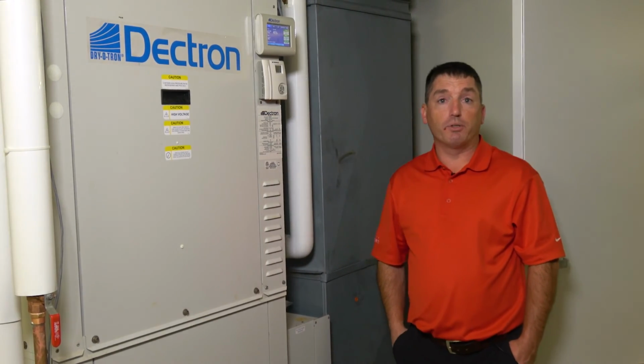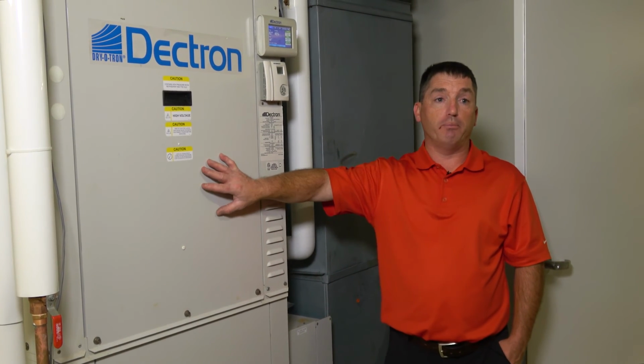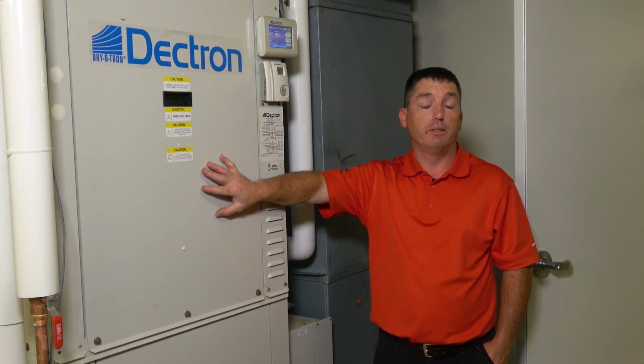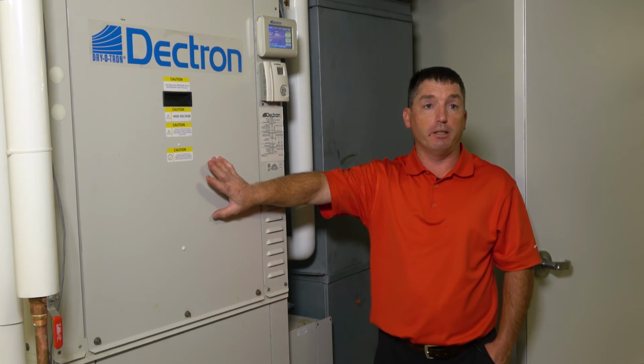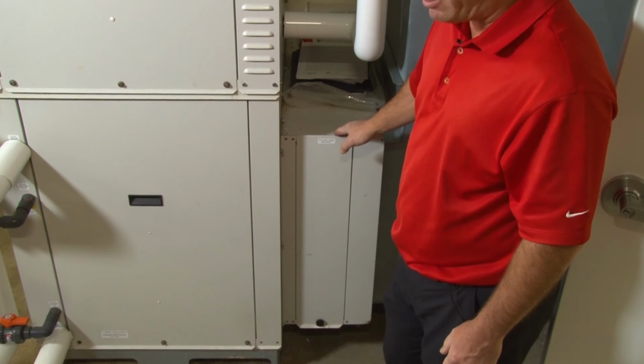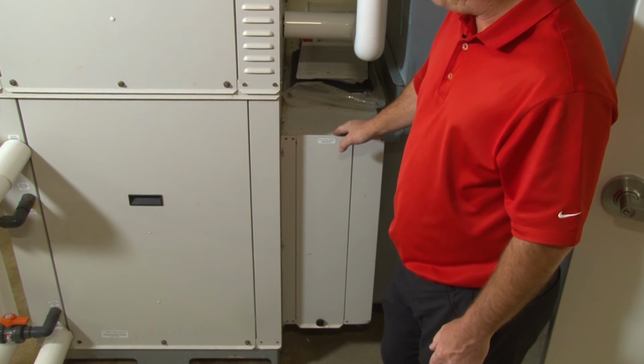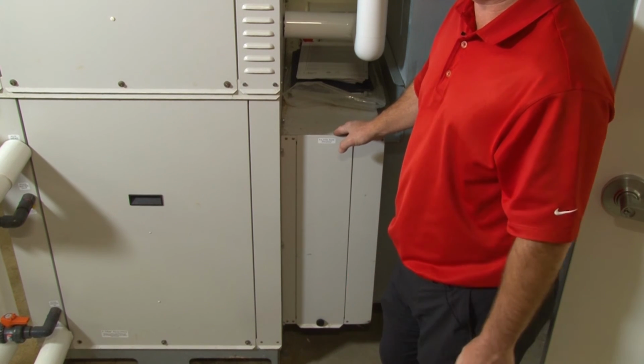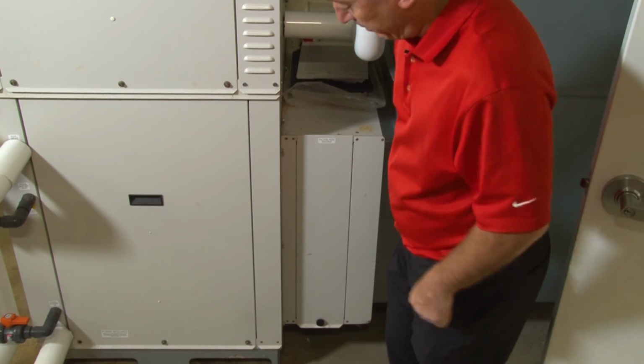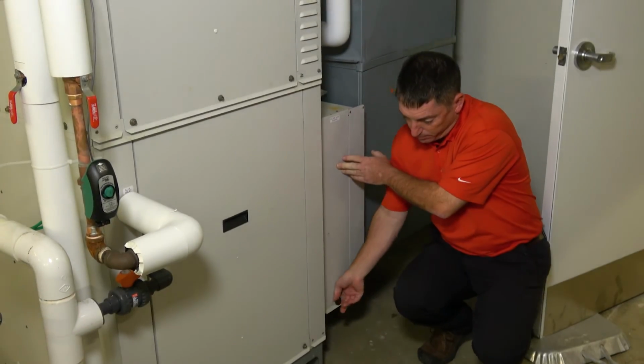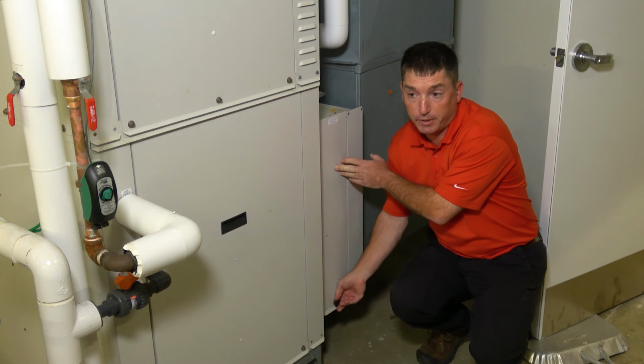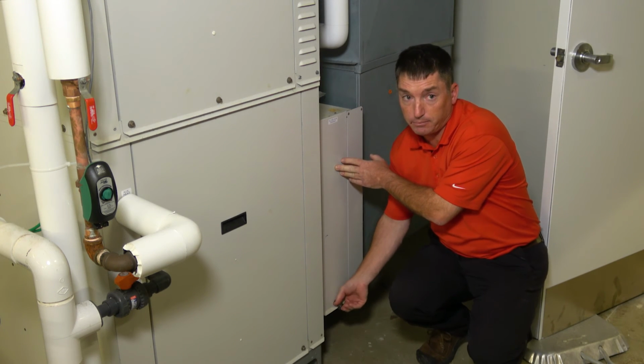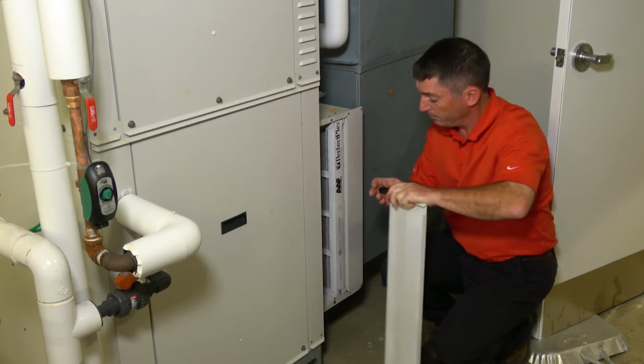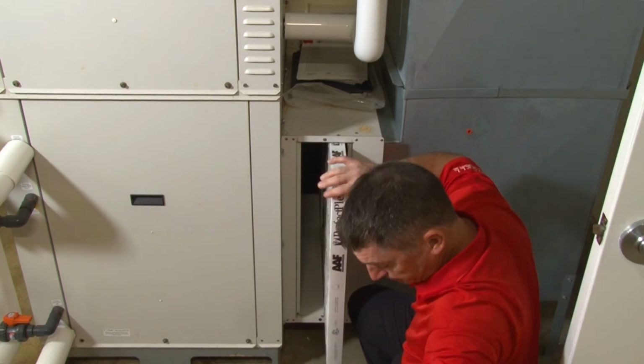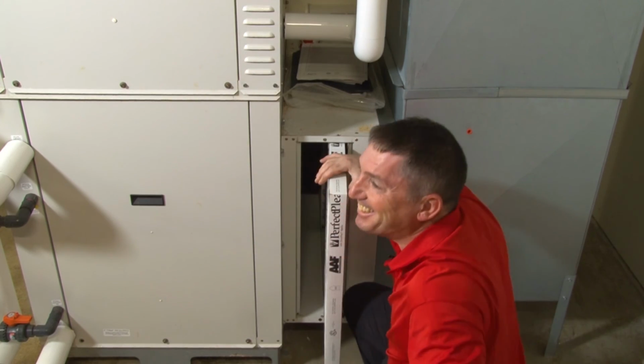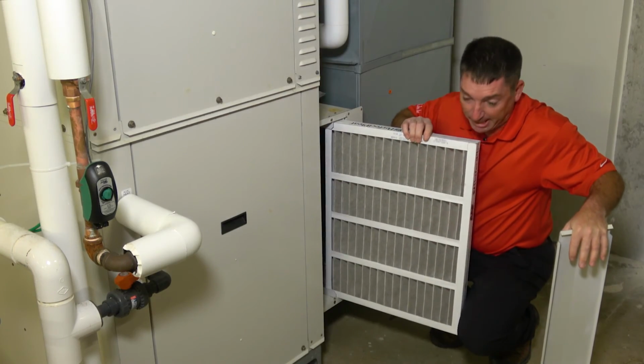As far as maintenance items go on the Dry-O-Tron, the supply blower is a direct drive, so there is zero maintenance to be done on that. In the return air, we're going to have two 2-inch pleated filters, just like we had in the air handling units on the roof. Simple thumb screw to remove the access door, and then the filters are going to slide out.